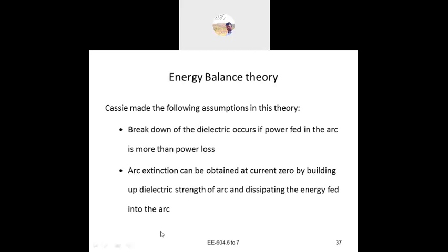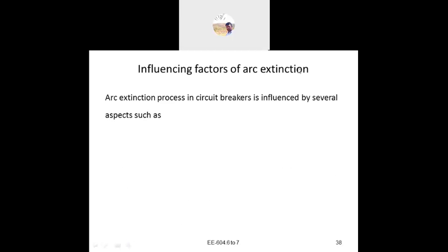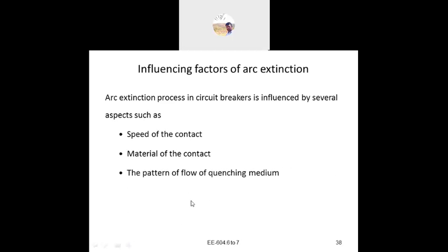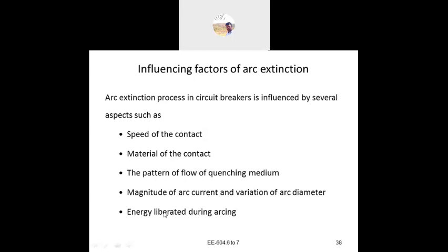So in this energy balance theory, what are the influencing factors of arc extinction? The arc extinction process in a circuit breaker is influenced by some factors: the speed of the contact, the material of the contact, and the pattern of flow of the quenching medium, either a chamber with gas flowing or a free flow where air escapes, as in normal air. Also the magnitude of the arc current, the variation of the arc diameter, and the energy liberated during the arc. These are the influencing factors for arc extinction.